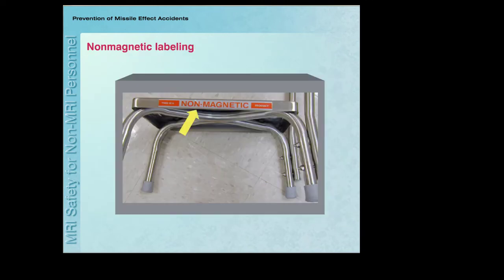When bringing devices and objects into the MRI system room, especially in response to an emergency, make sure ahead of time that they are not attracted to a magnet. If you are responding to an emergency, it is very important to know which non-magnetic rescue tools or devices are available and to only use these objects. Obviously, this should be determined in advance and the devices should be clearly labeled to indicate that they are non-magnetic.